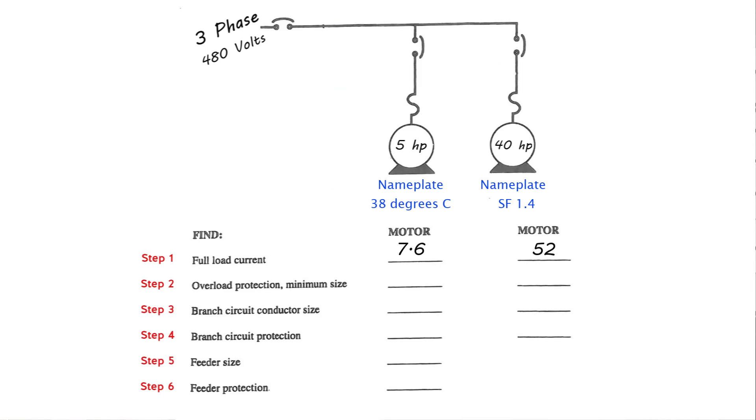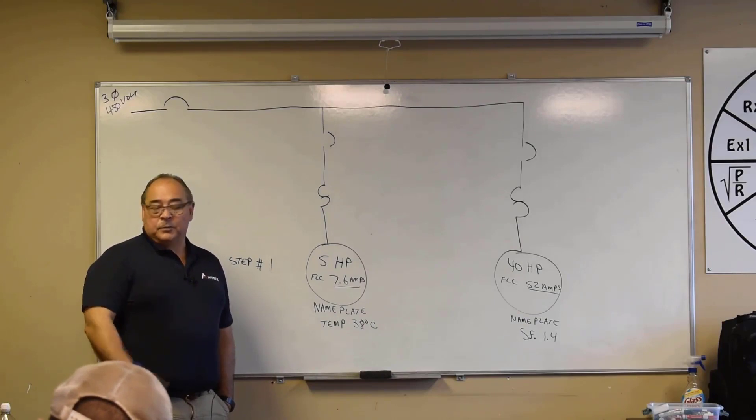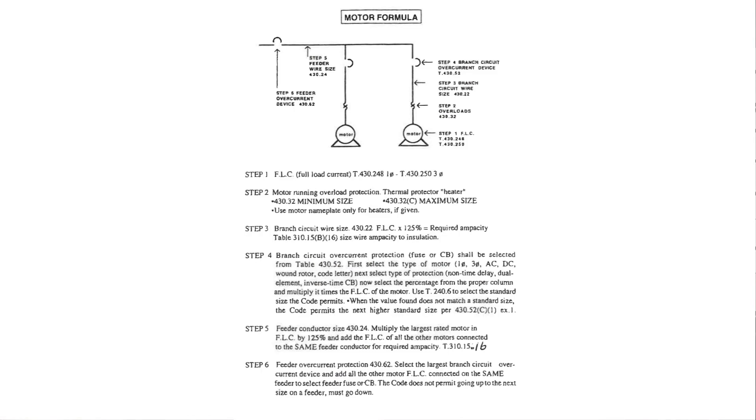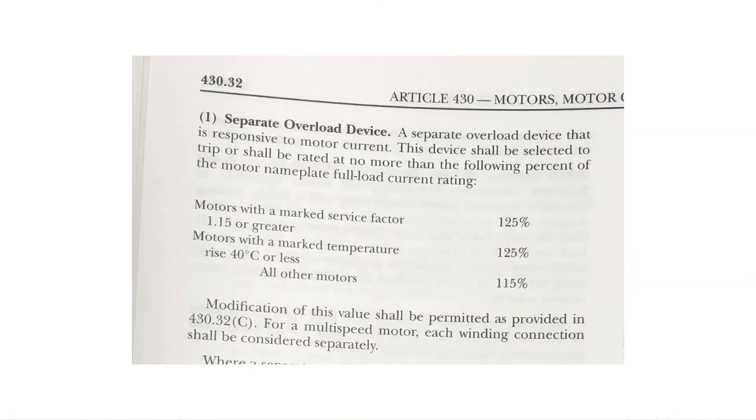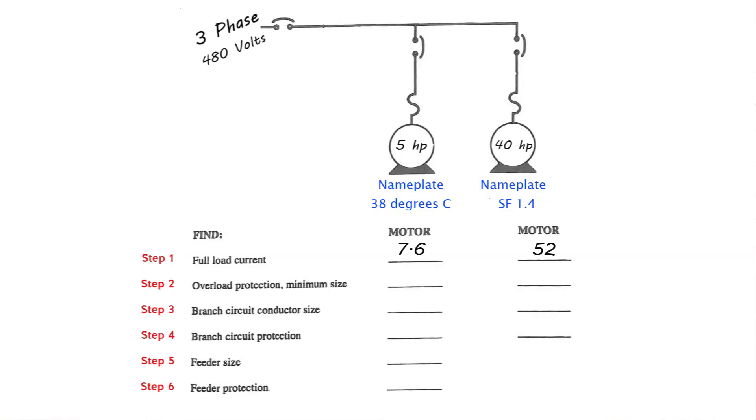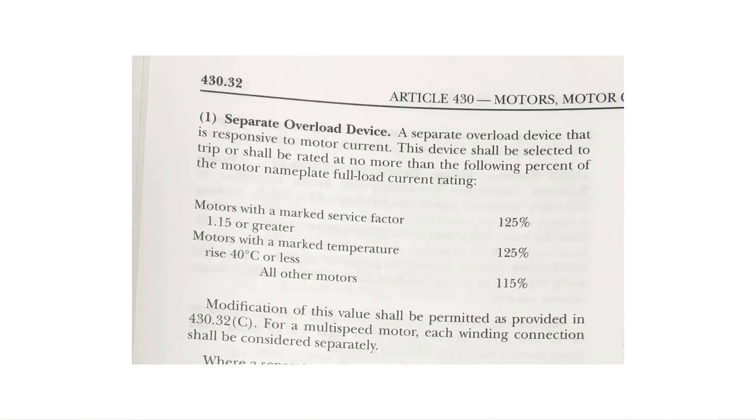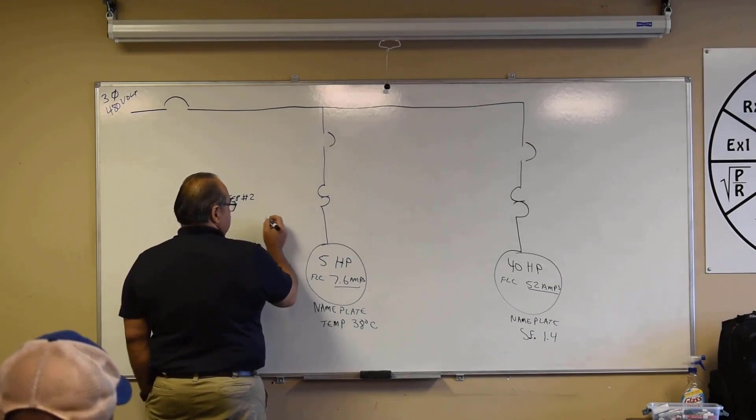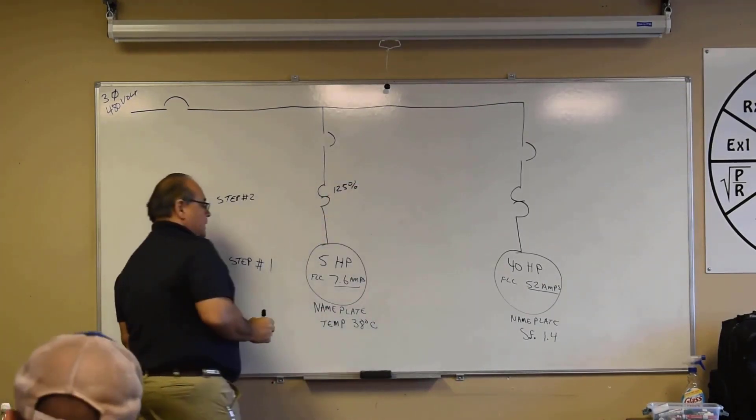Step number two talks about these overload relays or overload heaters, and we're going to use nameplate information for those. We're going to go to 430.32. Let's look for that. 430.32. On this five horsepower motor, we've got the nameplate rating, it says we got temperature of 38 degrees Celsius. What's our percentage we're going to use for that? Let everybody get to the right page. You are correct, 125 percent, because we've got a temperature rise of 40 degrees C or less, right? 38 degrees C is less than 40. So on this one it's going to be 125 percent. What's 125 percent of the FLC, right? So 125 percent times 7.6 equals what? 9.5 amps.